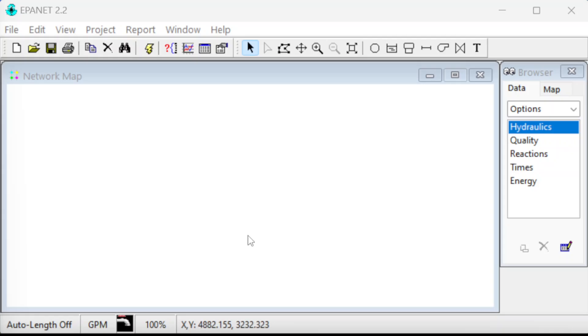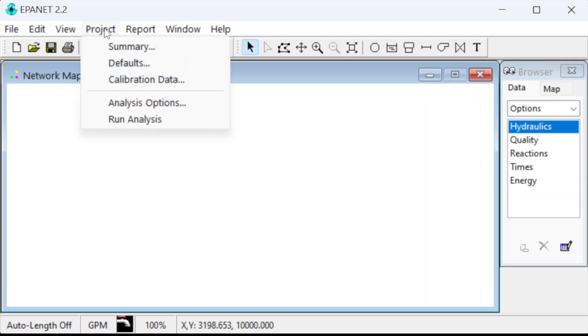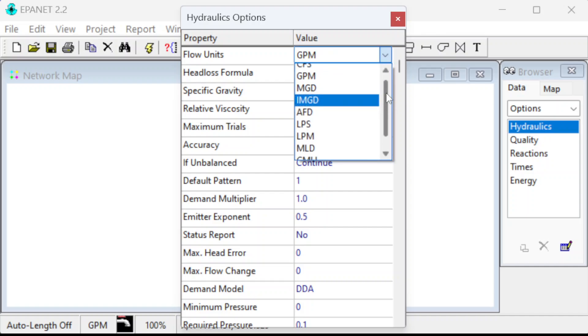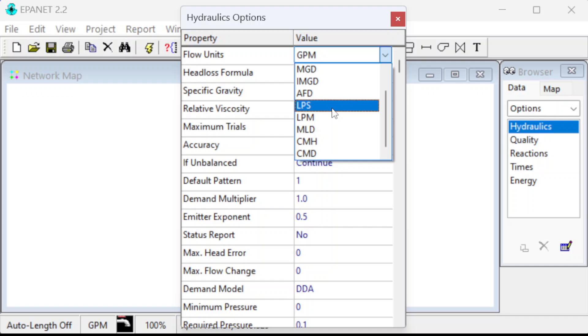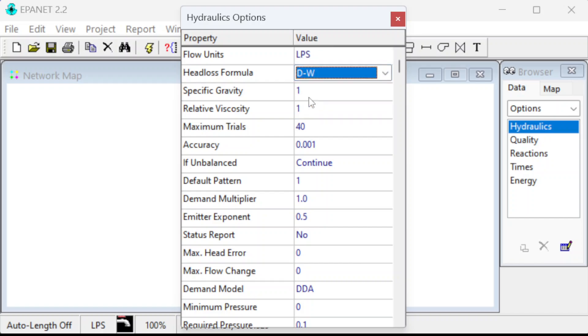Back to EPA net here. I opened EPA net in a new model and we need to draw everything. Before we do that, we want to set up all the project options. Let's change the units — this is currently in gallons per minute — so we're going to do this one in metric. The options are cubic feet per second, gallons per minute, million gallons a day, liters per second, liters per minute. Liters per second is what we need. And for head loss, we're going to use the Darcy-Weisbach equation instead of Hazen-Williams, so we'll switch that.